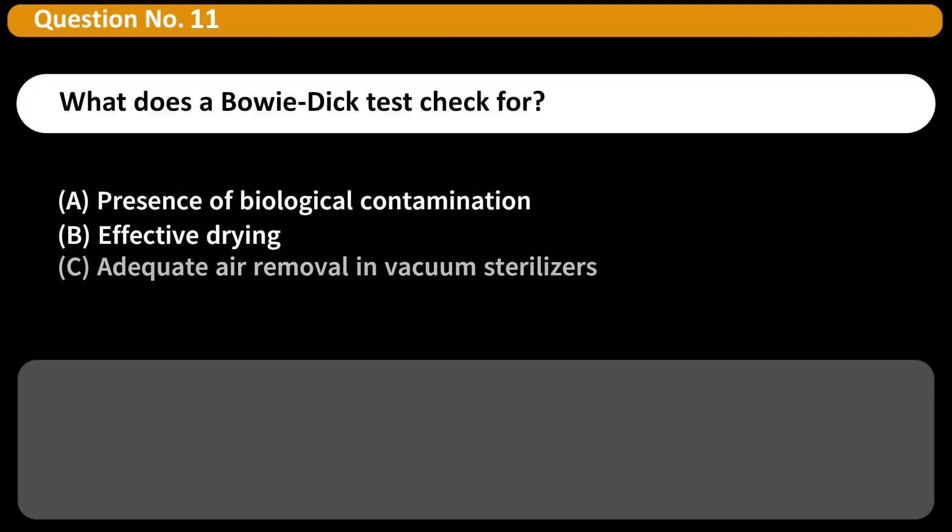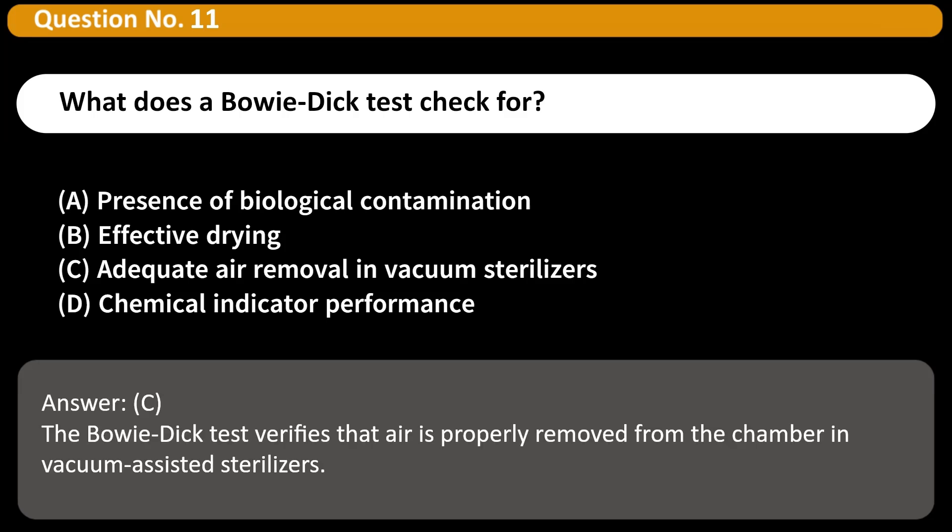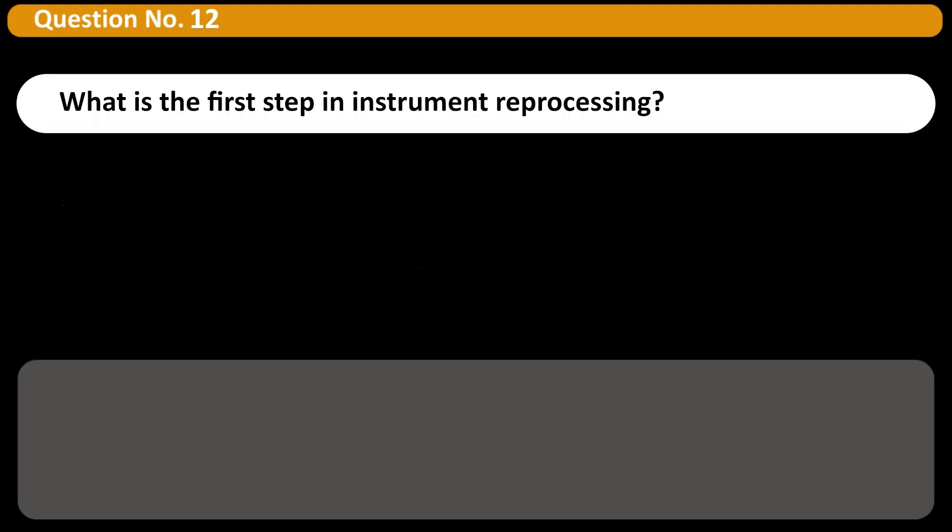What does a Bowie-Dick test check for? A. Presence of biological contamination, B. Effective drying, C. Adequate air removal in vacuum sterilizers, D. Chemical indicator performance. Answer C. The Bowie-Dick test verifies that air is properly removed from the chamber in vacuum-assisted sterilizers.